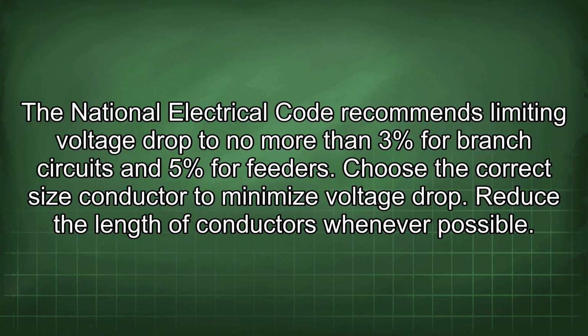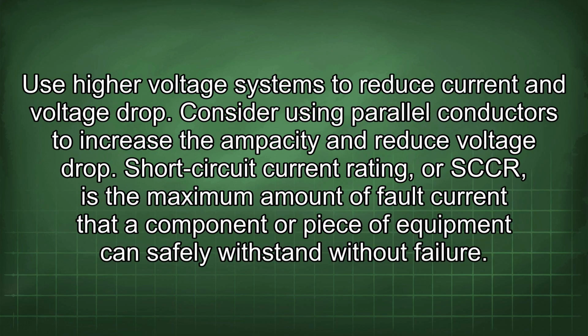Choose the correct size conductor to minimize voltage drop. Reduce the length of conductors whenever possible. Use higher voltage systems to reduce current and voltage drop. Consider using parallel conductors to increase the ampacity and reduce voltage drop.